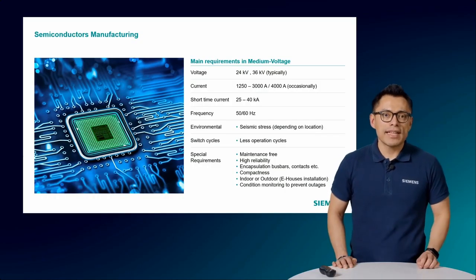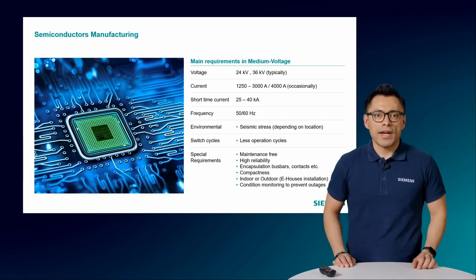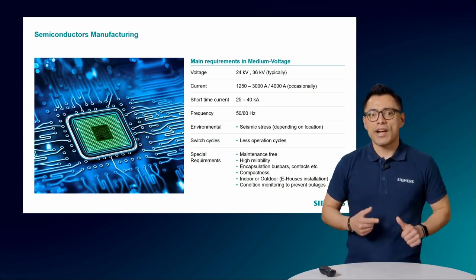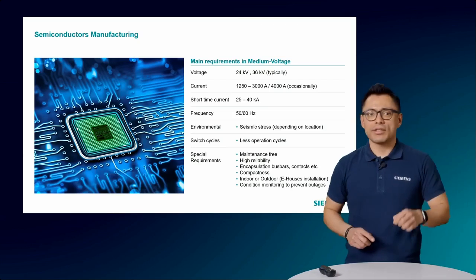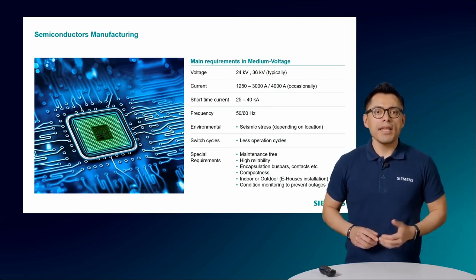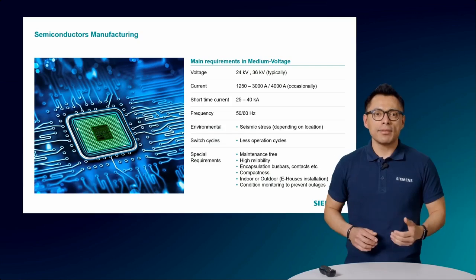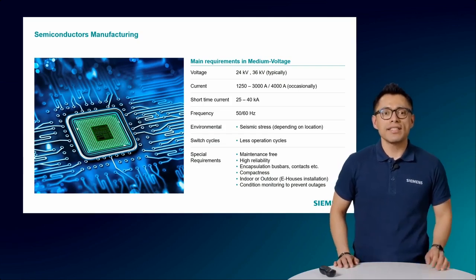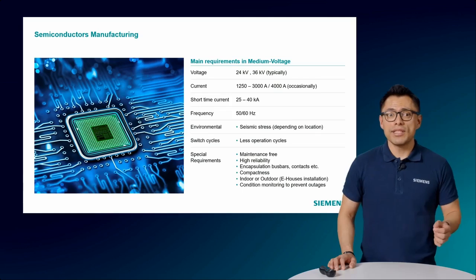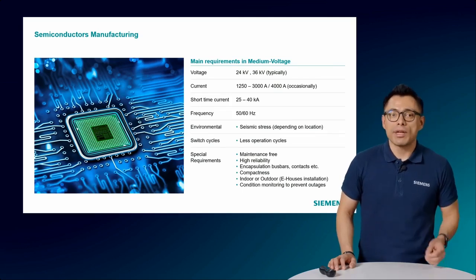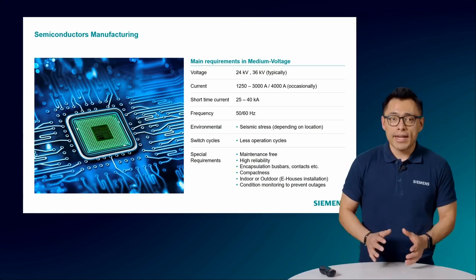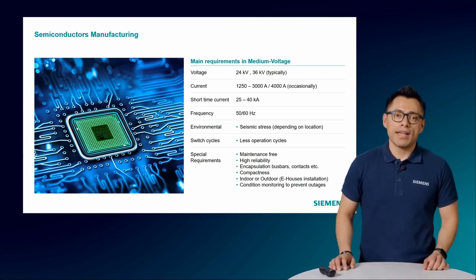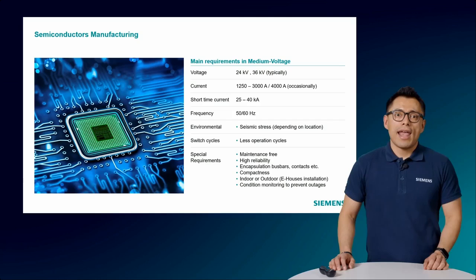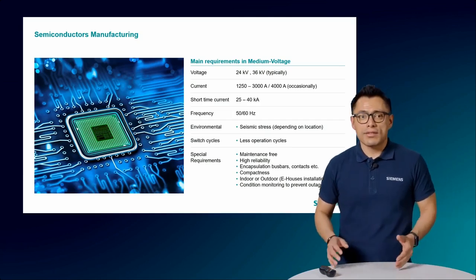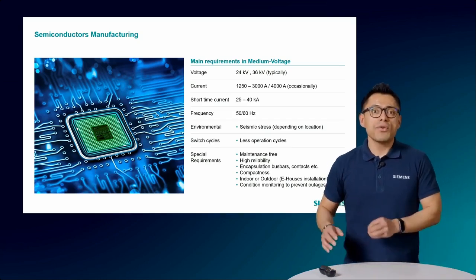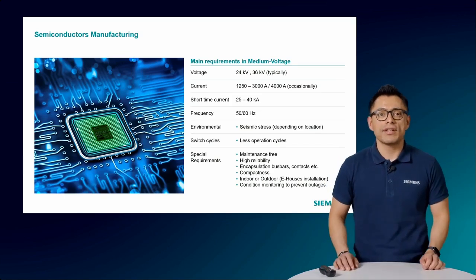Semiconductor manufacturing is an application with very demanding manufacturing processes. It needs a clean environment, stability, and precision. In this application, medium voltage switchgear needs to ensure a stable and precise power distribution to sensitive manufacturing equipment, reducing the risk of defects. Even more, medium voltage switchgear needs to be compact and seal-designed to minimize contamination. As the manufacturing process starts to demand higher power, an increase in the current capacity of the switchgear is also required.